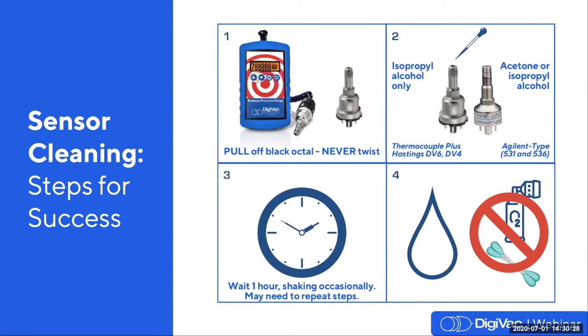So now we'll discuss our quick 4-step sensor cleaning process. First, we remove our sensor from our black octal connected to the coiled cable on the gauge. Remember, especially in the case of the VGT 500 sensor, there is a plastic key in the center that can break off if the sensor is handled roughly or uncoupled, or possibly attempted to twist in an effort to get it off. This is not a threaded connection, although it may look like one to the untrained eye. You simply need to hold the sensor in one hand and hold the connector with the other and pull it gently.